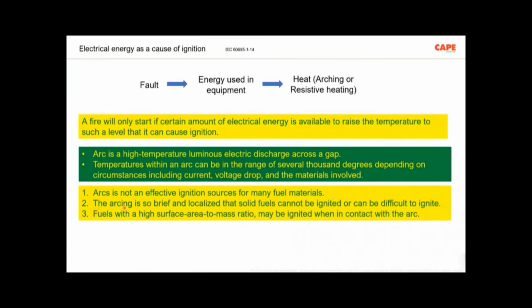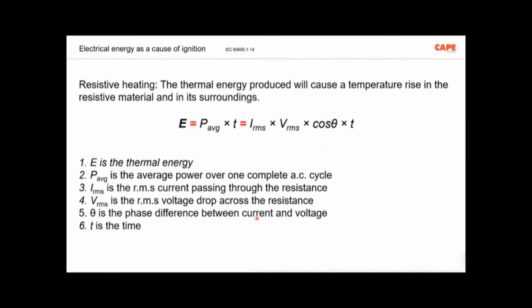Continuous arcing also is considered. The arcing is so brief and localized that solid fuels cannot be ignited or can be difficult to ignite. Fuels with a high surface area to mass ratio may be ignited when in contact with the arc. So basically, if we think that the arc is creating a fire, then we have to consider the other situations as well. Arc as such cannot ignite fire, provided there are no combustible things nearby. Most of the time, resistive heating is creating the failure or the fire. For resistive heating, the standard established how to calculate it: what is the energy involved, what is the duration involved, and how much energy and duration the equipment can withstand. All these things are very well documented, and these can be used for investigation and failure analysis.